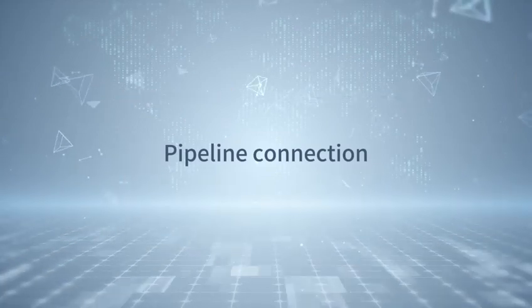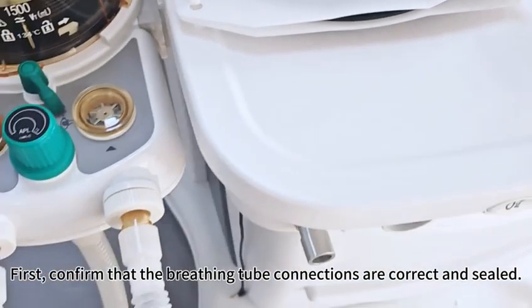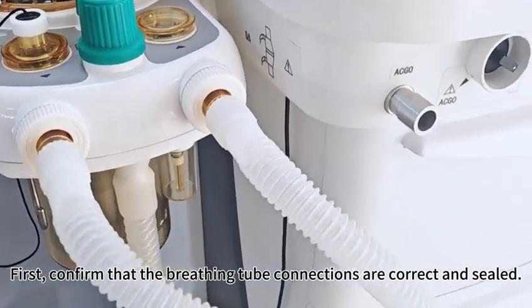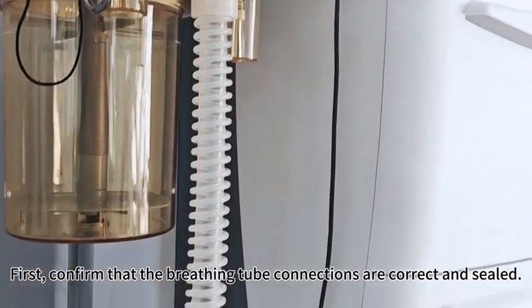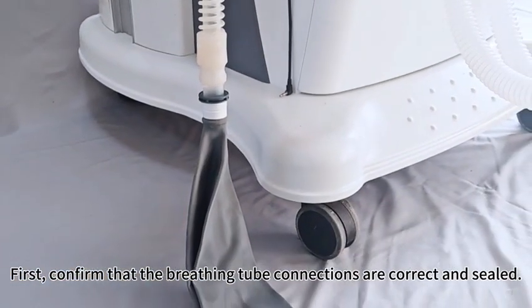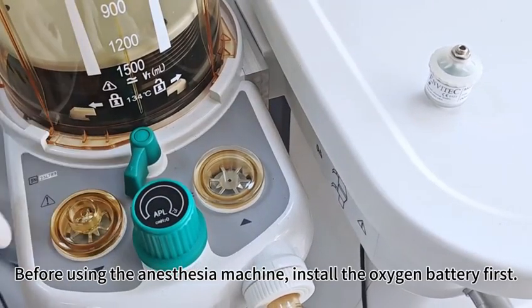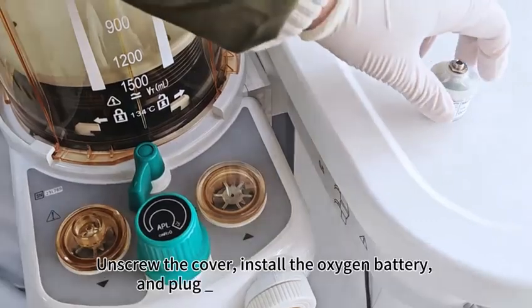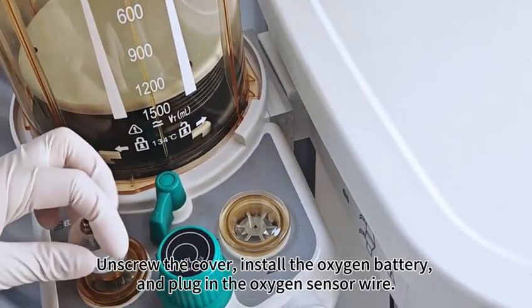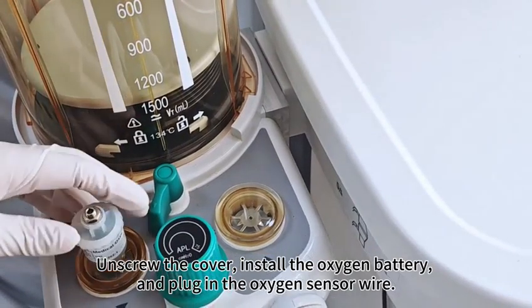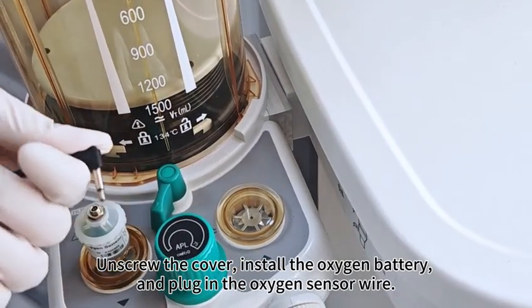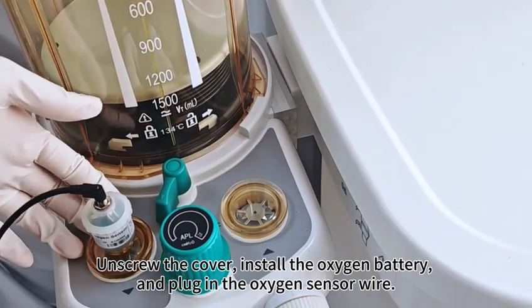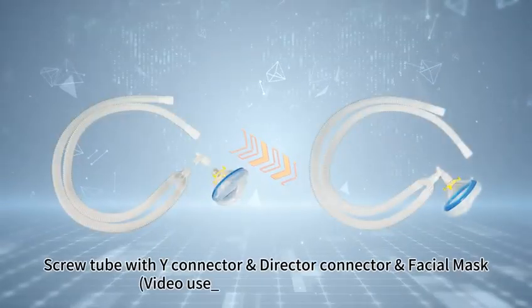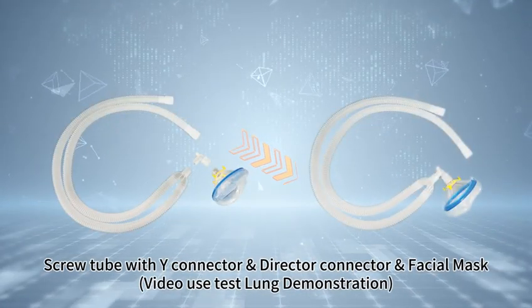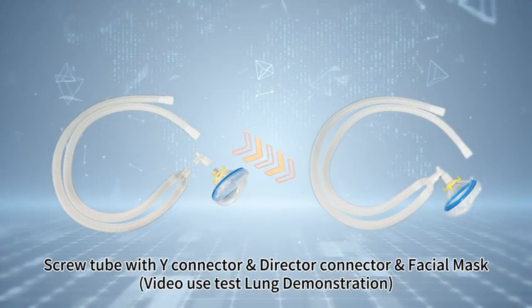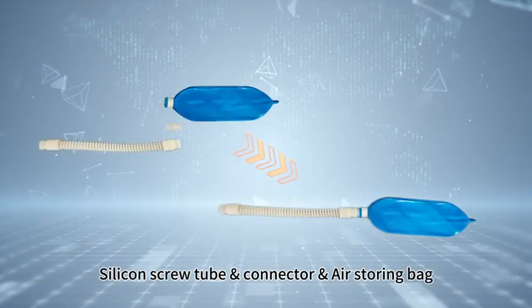Pipeline connection. First, confirm that the breathing tube connections are correct and sealed. Before using the anesthesia machine, install the oxygen battery first. Unscrew the cover, install the oxygen battery, and plug in the oxygen sensor wire. Screw tube with Y connector, director connector and facial mask, video use test lung demonstration. Silicon screw tube, connector and air storing bag.